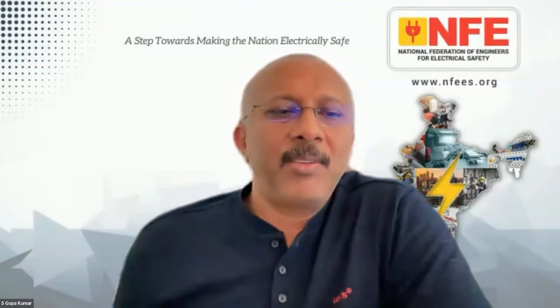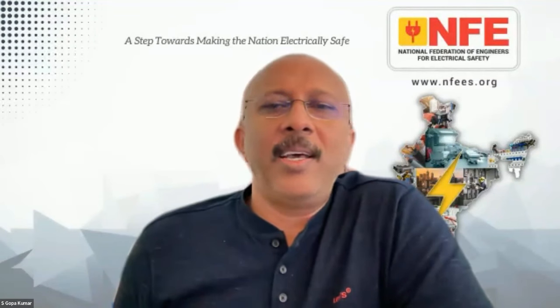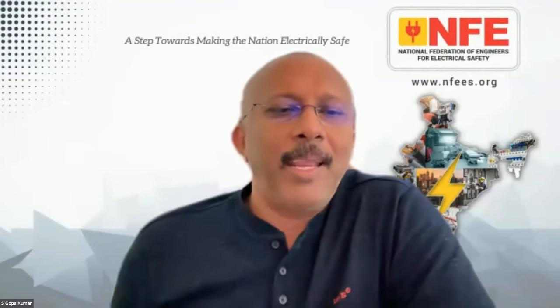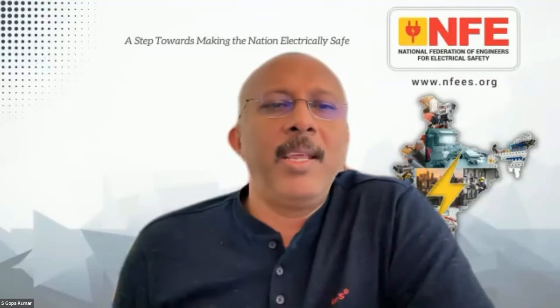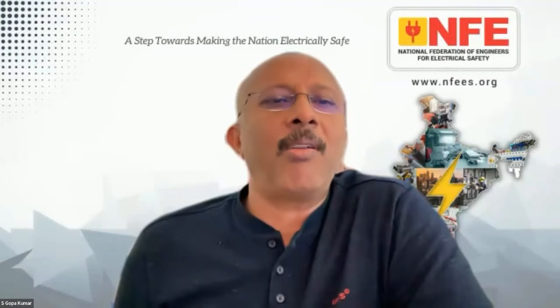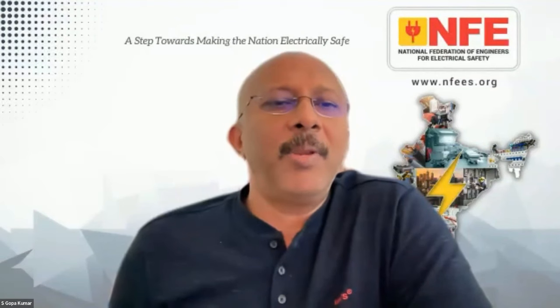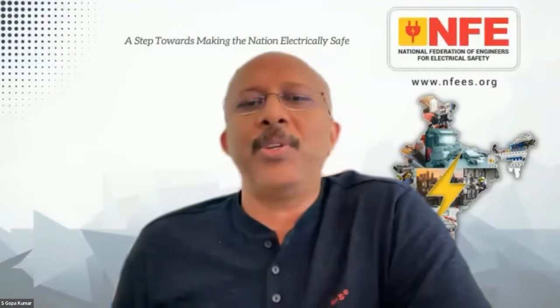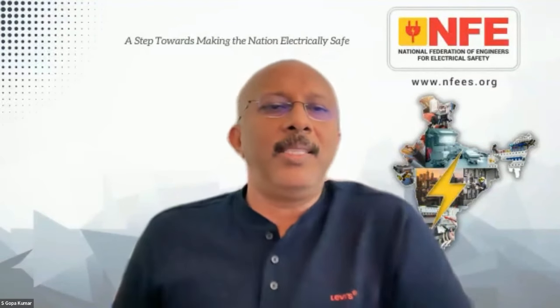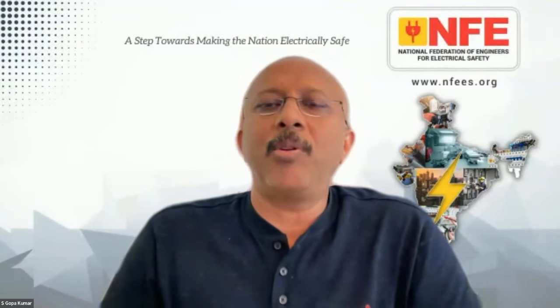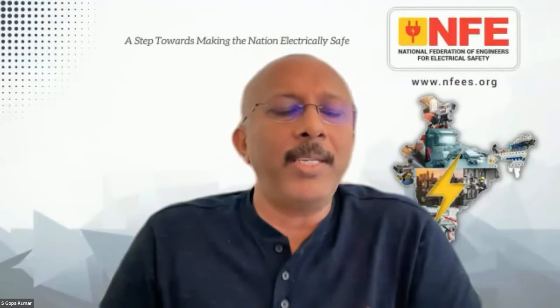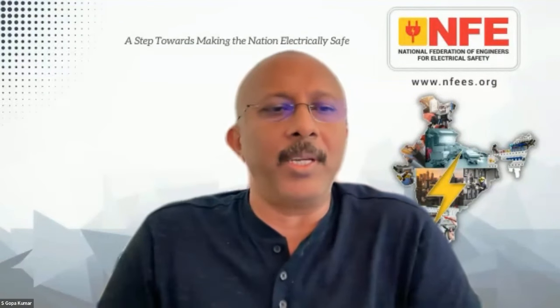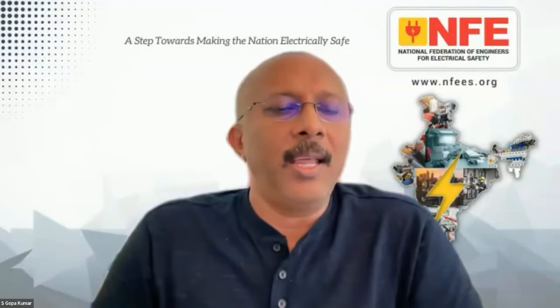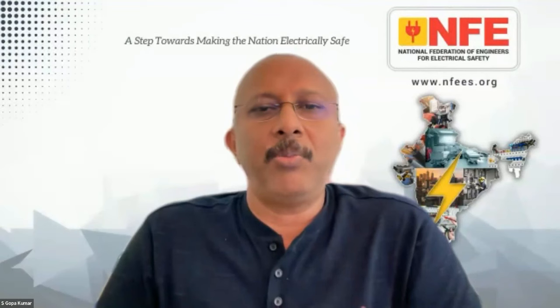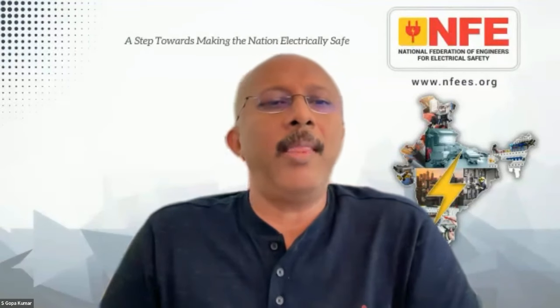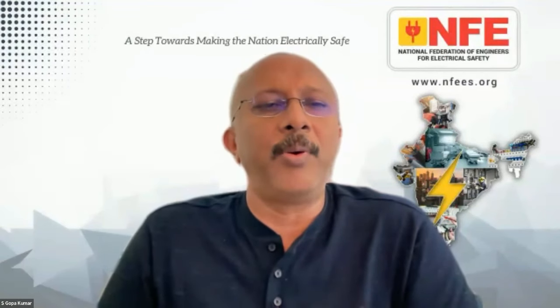Still, the problem is, first of all, the question. For example, lightning arrestor, what do you mean? Do you mean a surge arrestor in a distribution system, or a lightning air termination system in a building? This is the first question to be asked back. The regulation says, and there is a mistake in regulation number 74, that the lightning arrestor in the distribution system has to be connected to a separate earth electrode and then to the grid, to the plate.